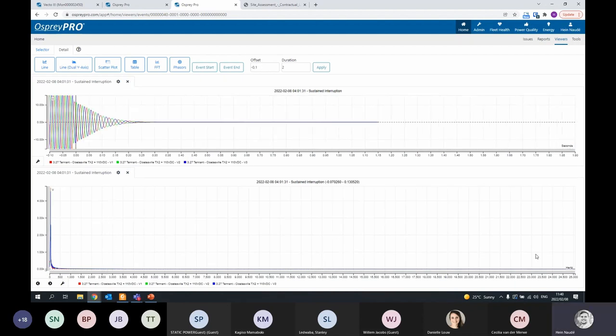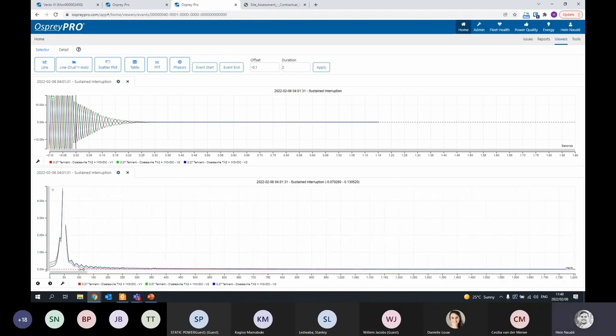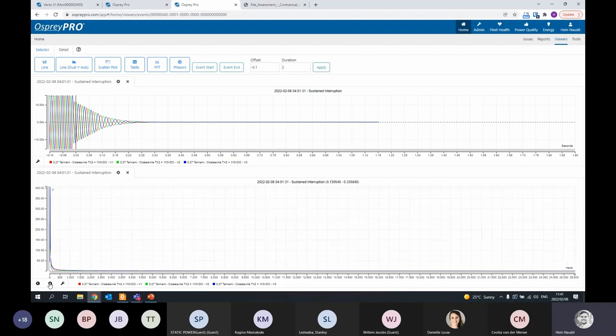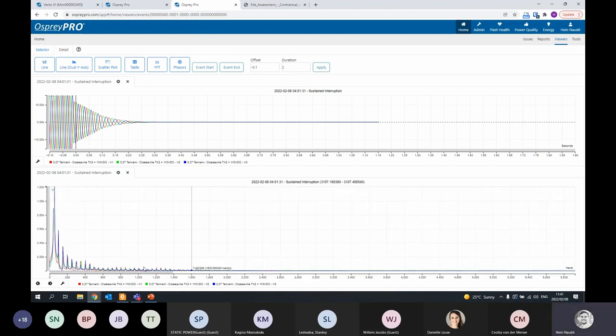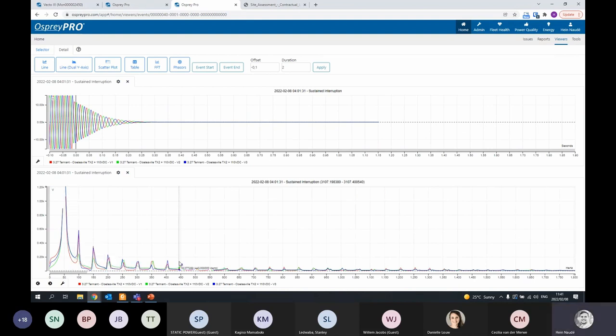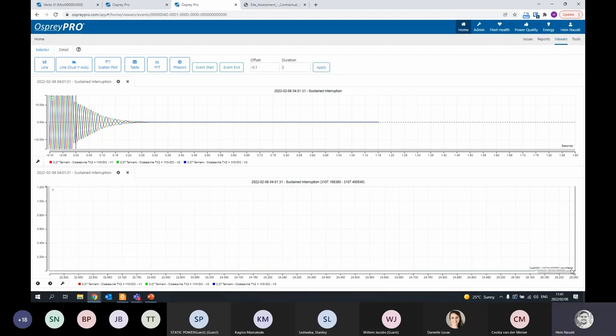Event start. So the first 200 millisecond block, you'll get your FFT of that. And then you can step through each 200 millisecond block of data. So in this case here, you can see the frequency spectrum for the second 200 millisecond block. And this is up to 25 kilohertz. You can do the same for the current waveform as well.